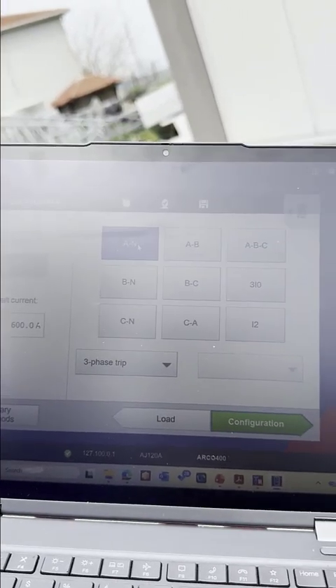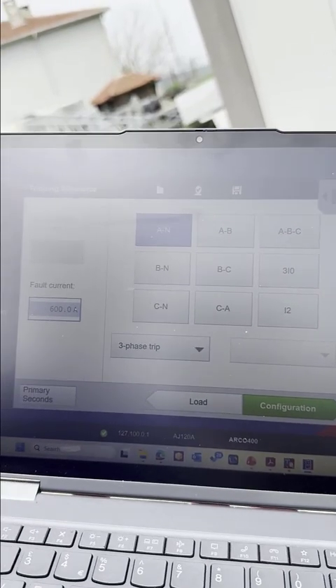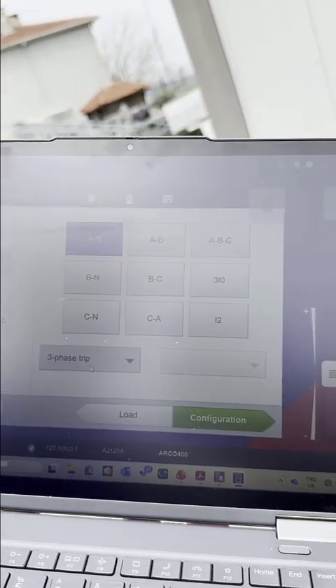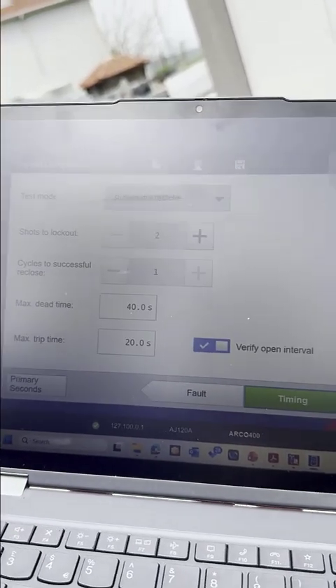You can now define a different fault loops. I will select a ground fault, which is a phase A to N fault, and now the fault current you can specify it as you like. As a 600 ampere, here is a 3-phase trip or single phase trip, depends on the scheme of the recloser application. Then you can go for the configuration screen. Now you have 3 modes.